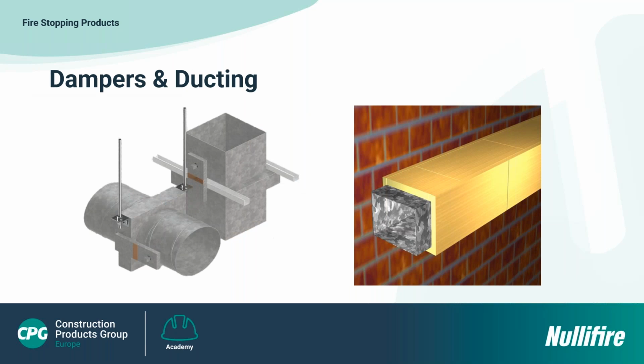Now, for fire-rated ducting material, mineral fiberboard is used here, encapsulating that ductwork and providing it with the required fire rating. Dampers within ductwork need to be given special consideration, and you must always consult the damper manufacturer for the method of protecting those. It's no good going to a manufacturer of fire protection materials. You need to go to the damper manufacturer, because that's another question that we're always getting asked. Cut out the middleman, go straight to the damper manufacturer, and they will let you know what method should be used.